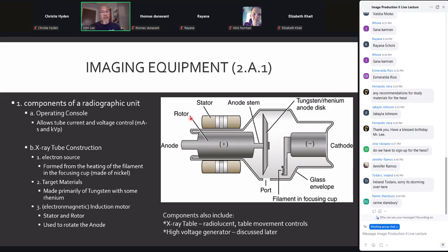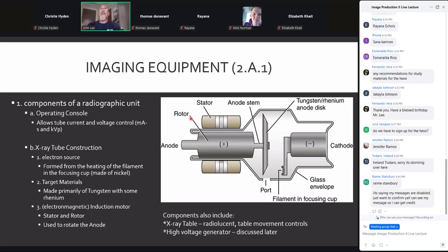And if you recall, the stator is a group of electromagnets that form a ring around the glass and goes over that anode end. And so the anode sitting inside the glass, when we rotor up, that first stage of exposure, those electromagnets turn off and on and move the polarity around. And then, of course, the anode tries to match that polarity or is repelled by it until we get the rotational speed required for our production.